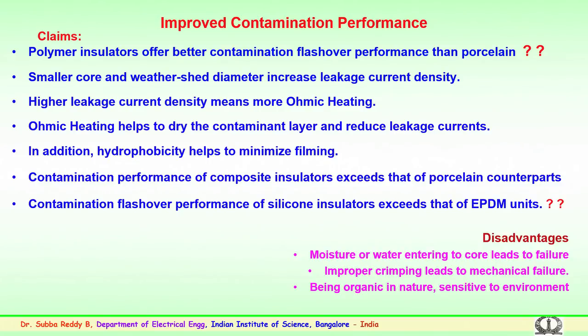Apart from that, the polymer insulators have a smaller core and weather shed diameter in comparison. The petticoats or shed dimensions of porcelain, ceramic or glass are much bigger in size, bulky in size. Here the material is organic, as mentioned, so they are lighter in weight and the shed diameter is comparatively lesser than the porcelain or glass insulator. This increases the leakage current density. Higher leakage current density means more ohmic heating. So, this is one of the advantages.